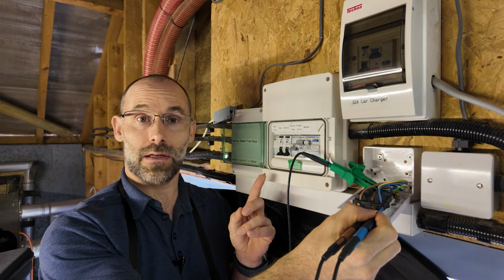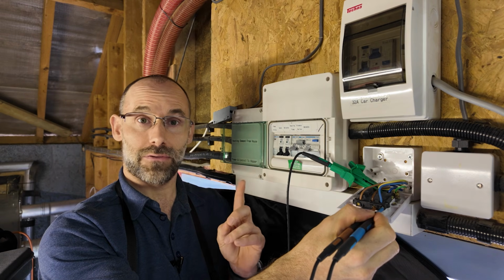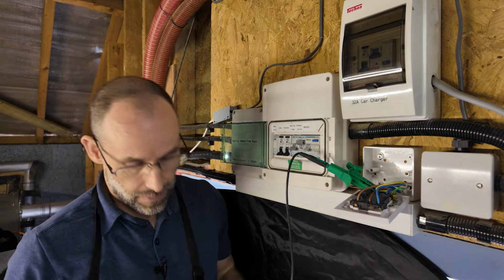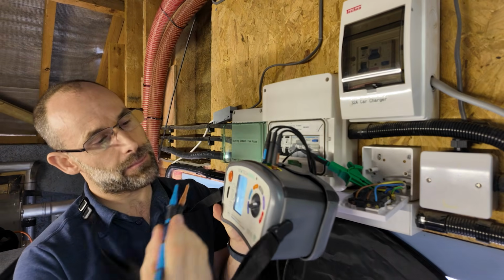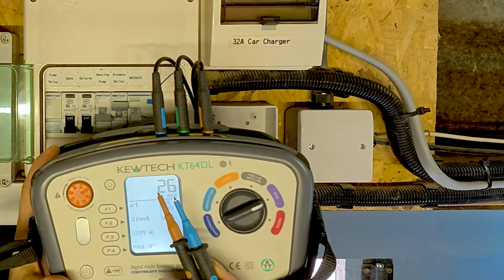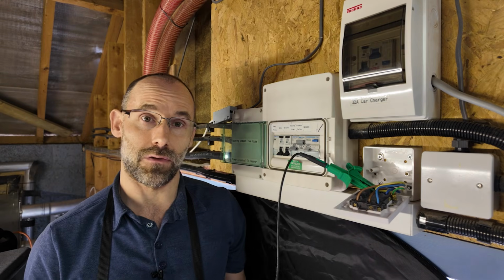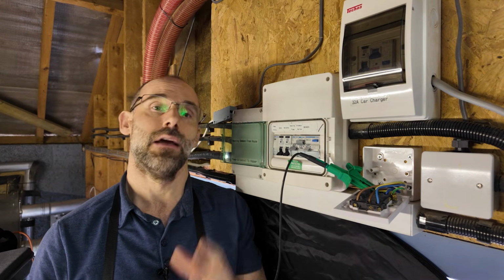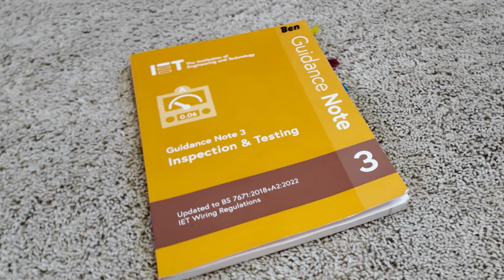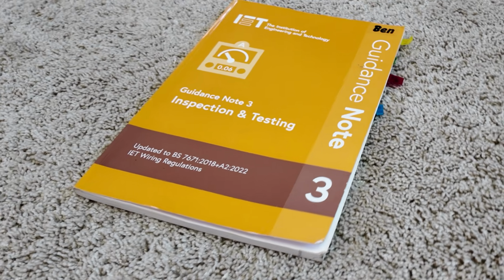And it's not only going to check that it trips, it's going to check how fast it trips. So you heard it trip, clunk there, and then it tells me that that happened within 26 milliseconds. Now that's well within our regulation times here, but to know what the time should be, you need to know how to look it up in the regulation book, which is a chunky book, so that's no mean feat.